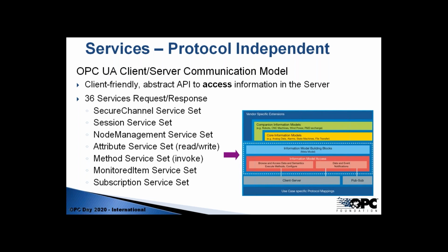So we have secure channel services, session services, node management services, attribute services, which are probably the most interesting because that's the read and the write of the values. We have a method service set where we can invoke methods, and also a monitored item and subscription service set where we do the notifications of data and events.